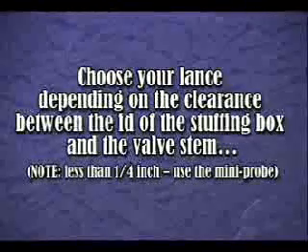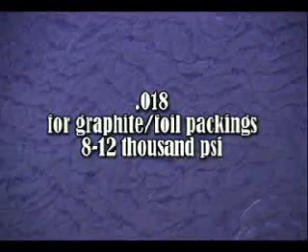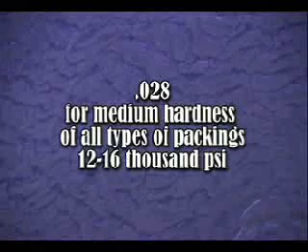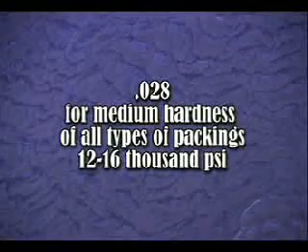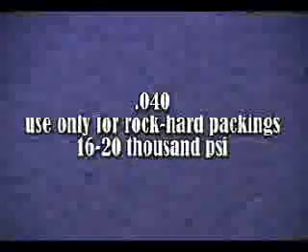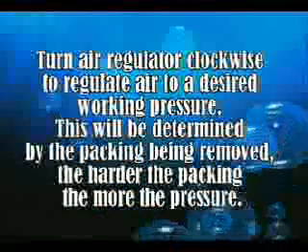There are three standard orifice sizes. .018 for graphite foil packings, using 8,000 to 12,000 PSI. .028 for medium hardness of all types of packings, using about 12,000 to 16,000 PSI. .040 for only the rock-hard packings, which will use about 16,000 to 20,000 PSI. Lances are shipped straight and can be bent up to 90 degrees. Turn the air regulator clockwise to regulate air to a desired working pressure. This will be determined by the packing being removed — the harder the packing, the more the pressure.